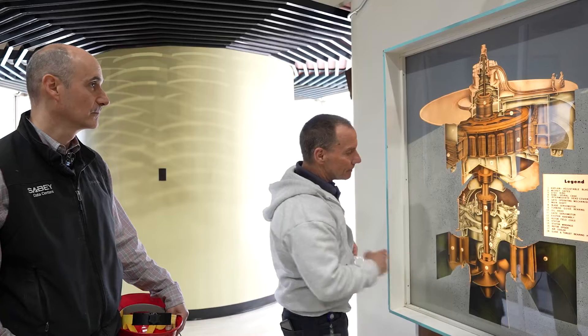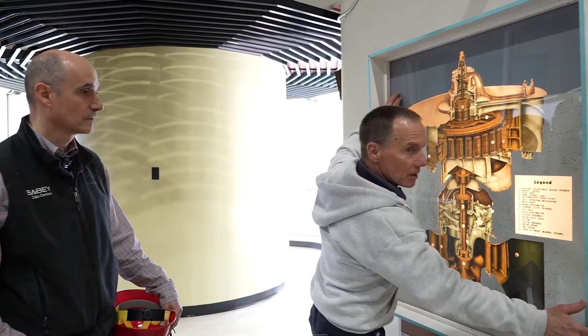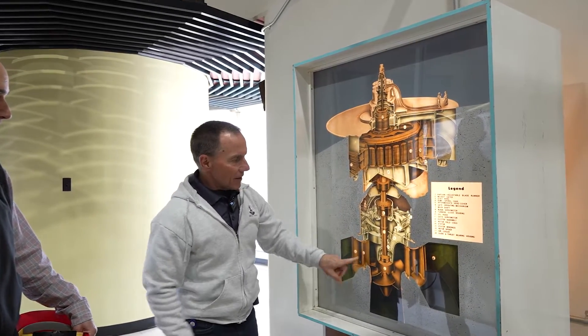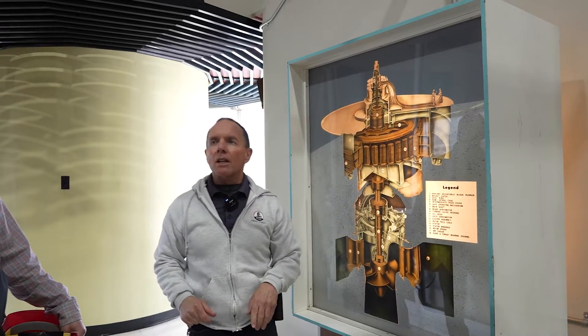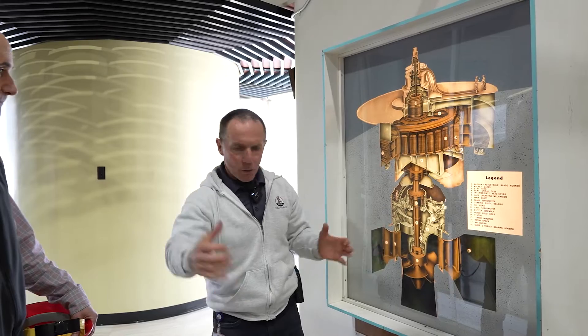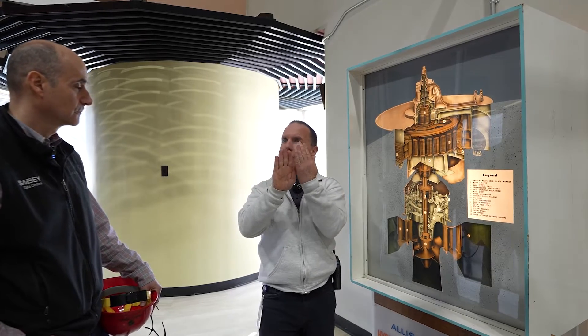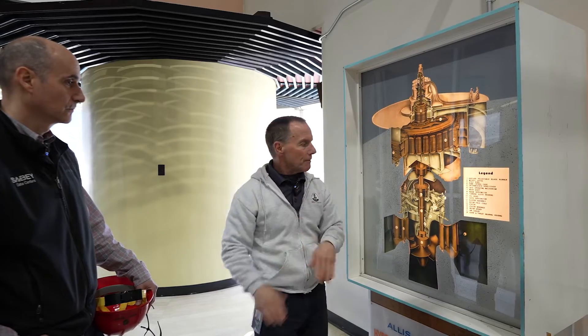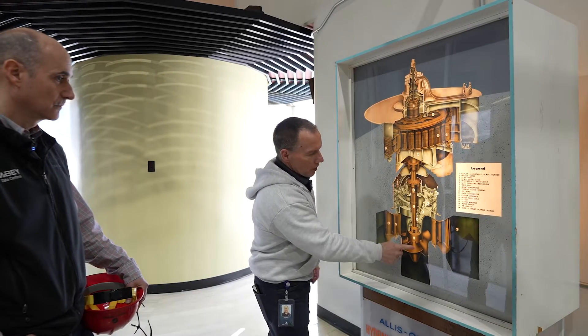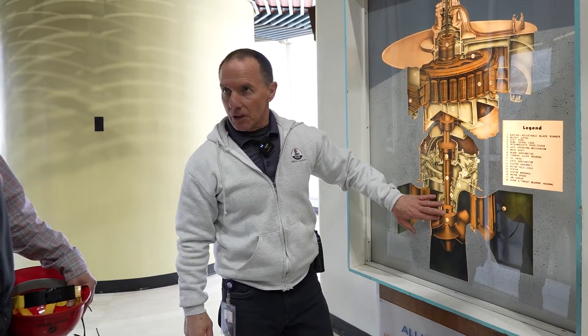This is one of our units. Imagine this is the top side of the dam and this is the bottom side. We're going to drop about 8 million gallons of water a minute, 92 feet. These are wicket gates, and they go all the way around the turbine — just like vertical blinds in your house. There's an O-ring with two governing arms. As we turn that O-ring, all of those wicket gates either close — that shuts the unit down — or open, letting water come in, pressure builds up, and we go on the grid.